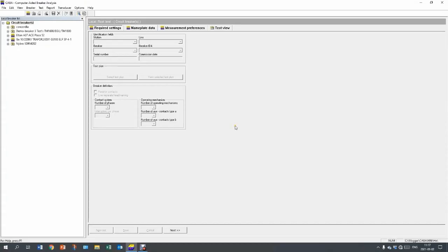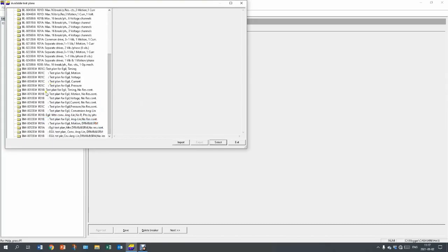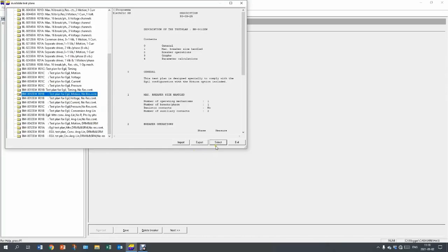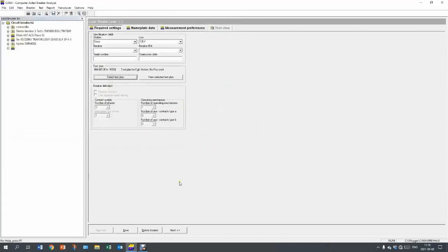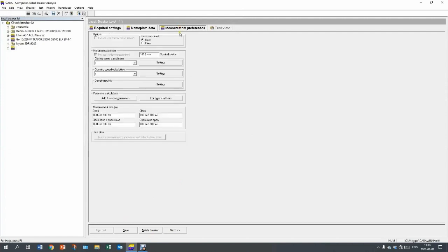I've connected the EGIL with my PC. I start with creating a new object, a new breaker, and I give it a name. I select the test plan, and I need an EGIL test plan, and I want to use one with motion and no resistor contact. So I select BM8012 EV. I continue with setting the stroke. I use 100 millimeters because I don't know the stroke of this transducer, so I use a simple value as 100 because it's easier to calculate if I get more information in the future.